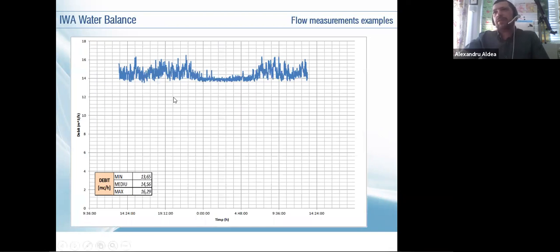Okay, this one, let's see if you can spot the night flow. This is the night flow, and this little variation here is actually the consumption. It was a case where I had an ILI of around 80. It was a very small network, and long story short, when they rehabilitated it, they built another network 10 times bigger than that, and they renounced this one, like 2 kilometers or something. But today, this is the biggest ILI that I could find in Romania, at least.